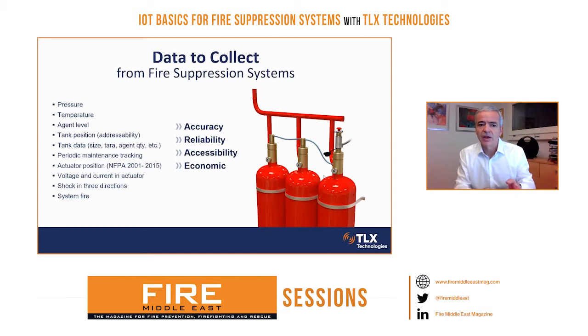All of those variables, added to some innovations that TLX is working on today, like recording elaborate data on what's going on with those actuators—measurement of voltage and current through the solenoid, or information about movement, since accelerometers are integrated into the actuators—means all of that is being recorded. So an event recorder will have all that information stored. If there's an accidental discharge, or an actuator that's not properly positioned, all of that information will be available, with the possibility of having it all in the cloud, accessed and reported to facility managers or service companies.